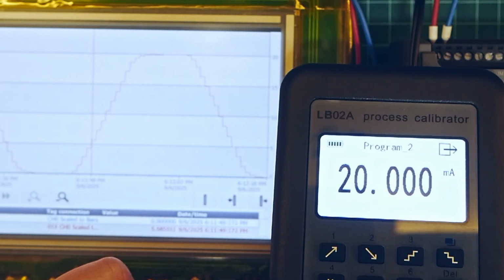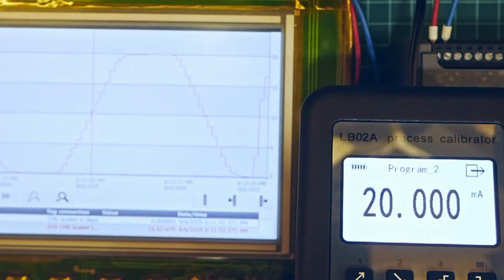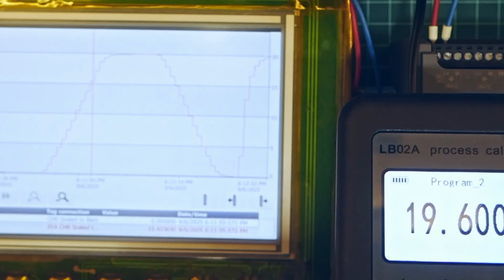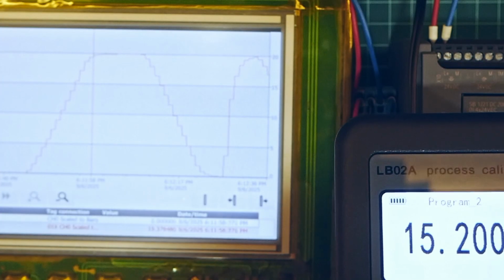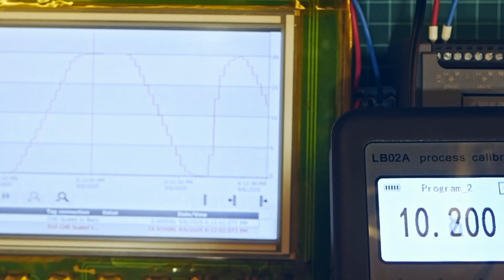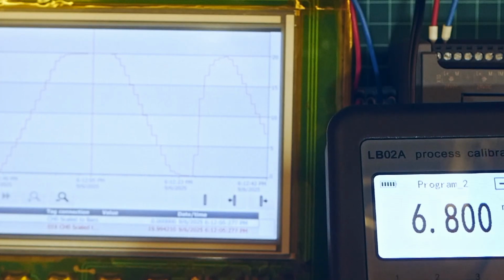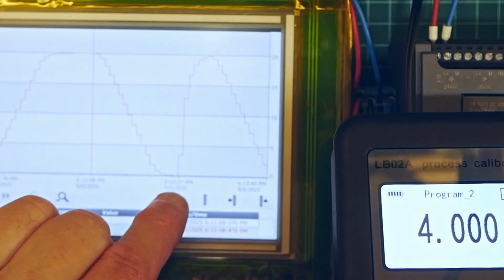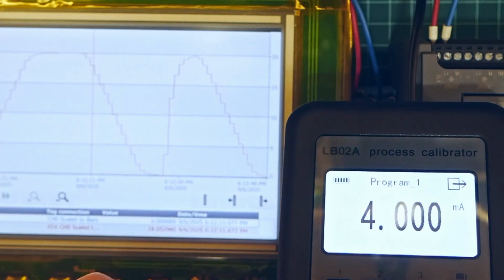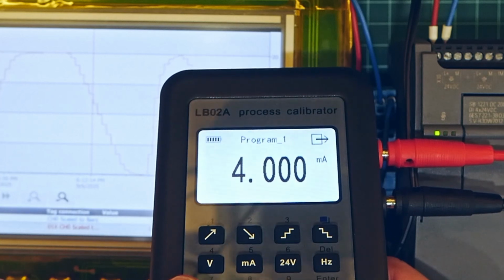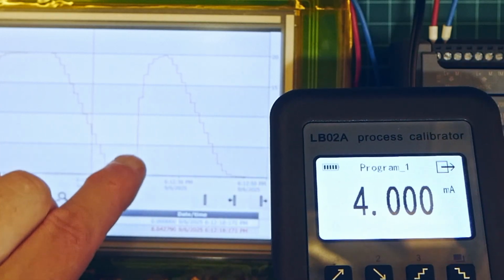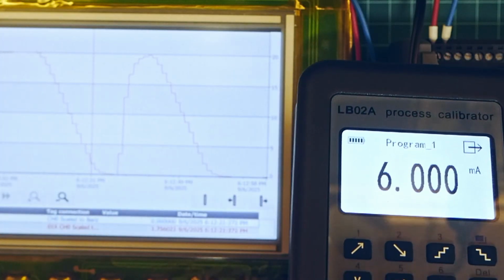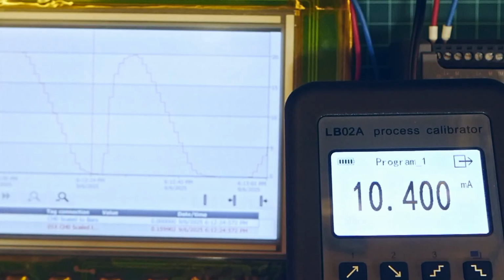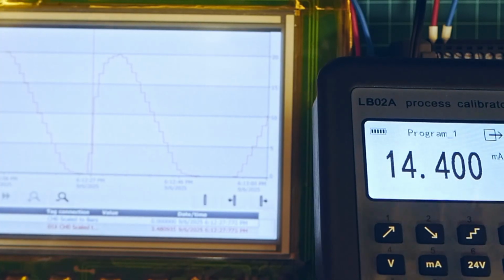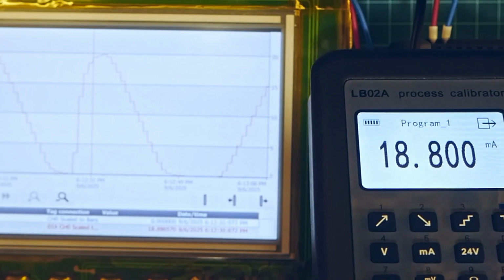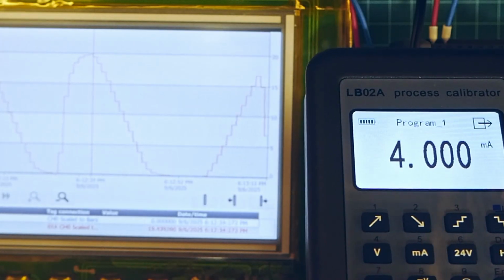Okay, let's go. There is a program 2, so it's kind of a little bit different. From the low limit it jumps to 20 milliamps and then stays there for set point time and then slowly ramps down. So as you can see, it's a little bit different. And then we will have program 1. So it's kind of very similar to program 2, but it's in reverse. So basically it ramps up slowly to high limit and then stays there for set point time and then drops to low limit and starts again.